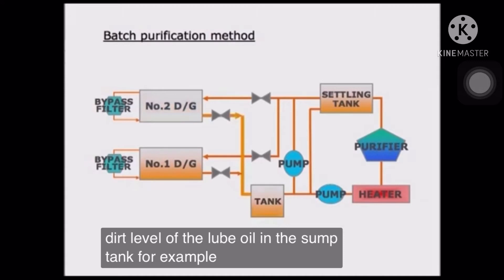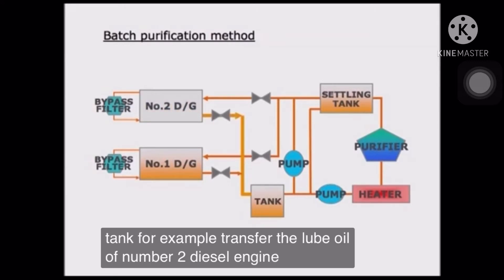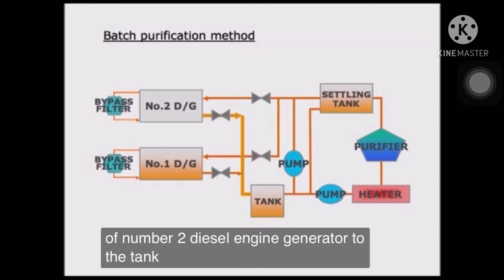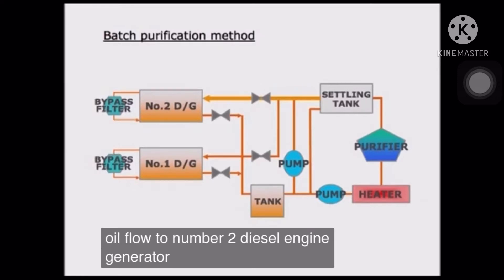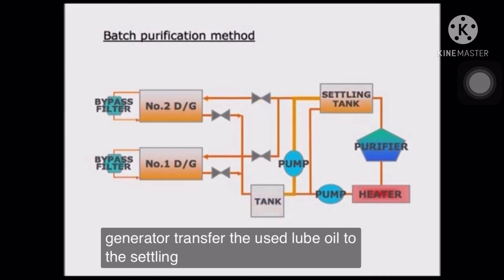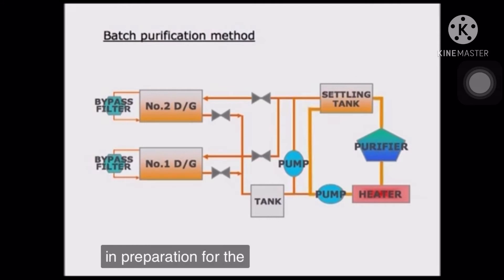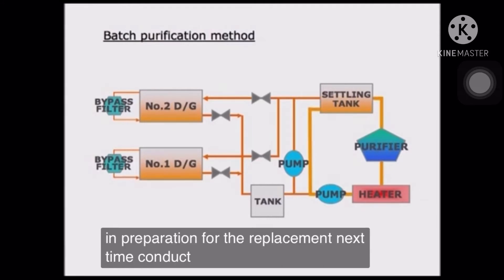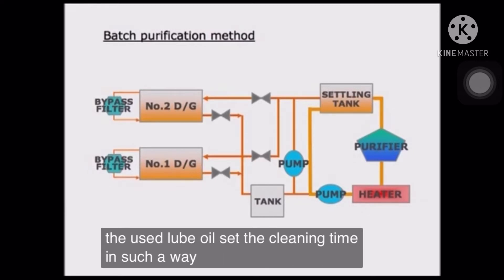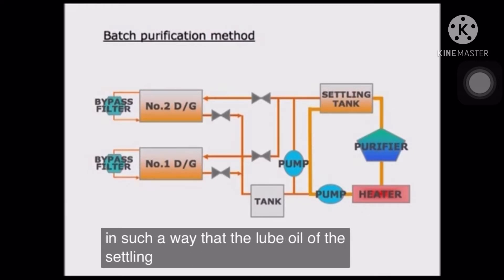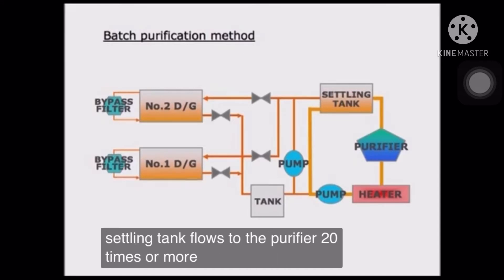For example, transfer the lube oil of number 2 diesel engine generator to the tank. Let the already cleaned lube oil flow to number 2 diesel engine generator. Transfer the used lube oil to the settling tank. In preparation for the replacement next time, conduct the cleaning treatment for the used lube oil. Set the cleaning time in such a way that the lube oil of the settling tank flows through the purifier 20 times or more.